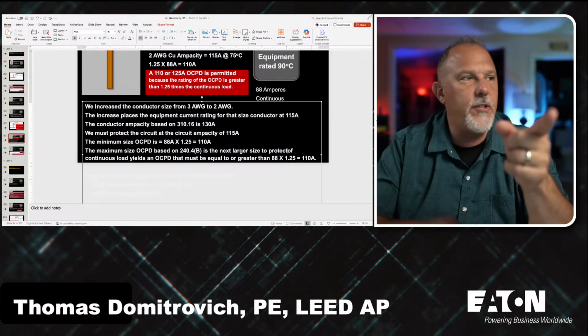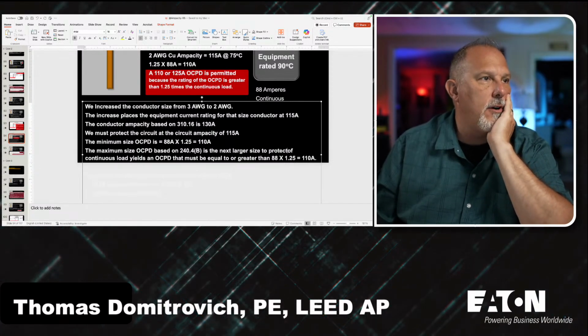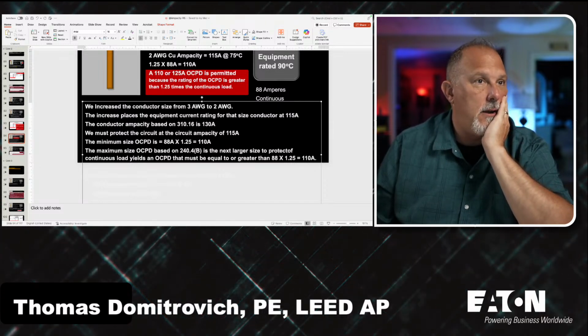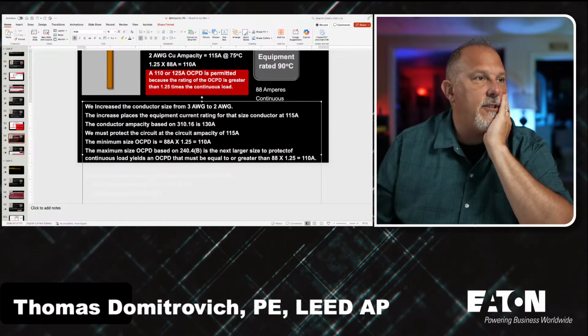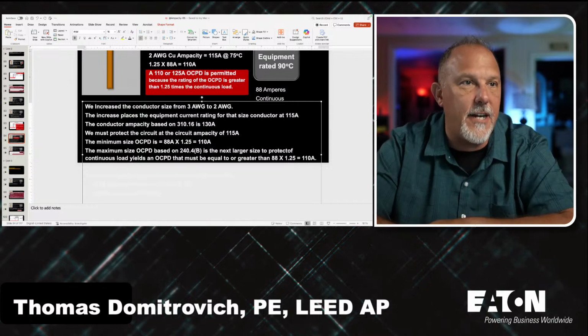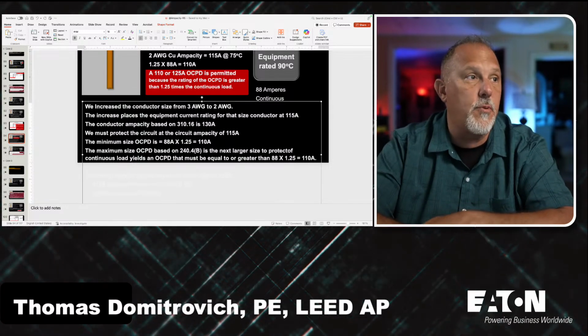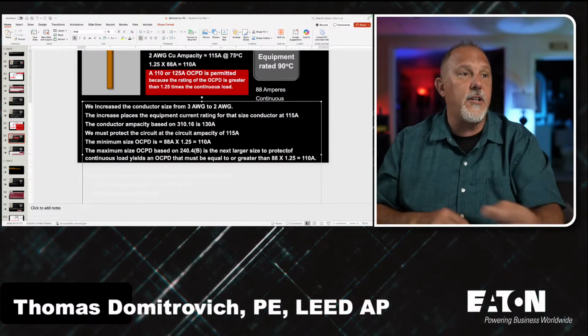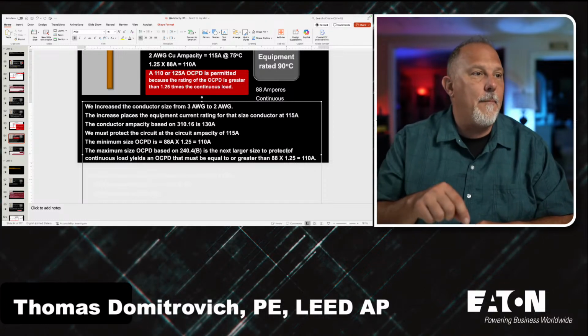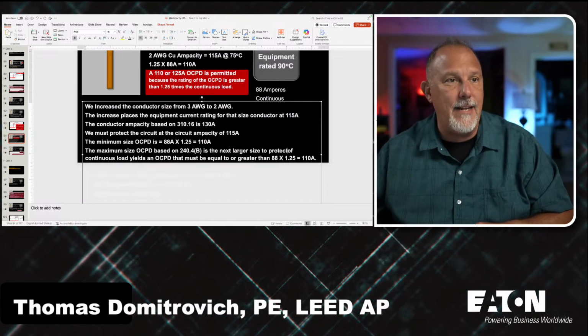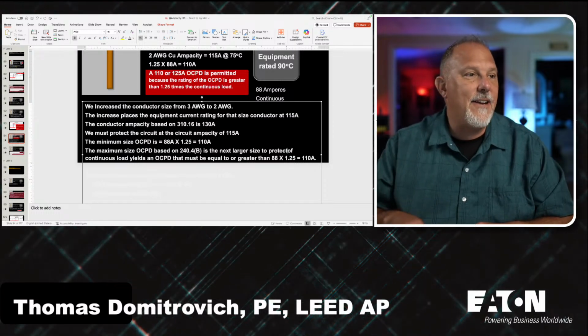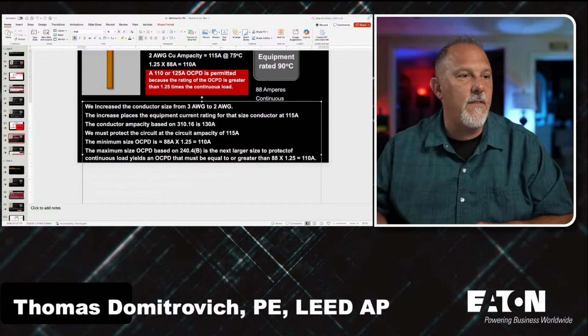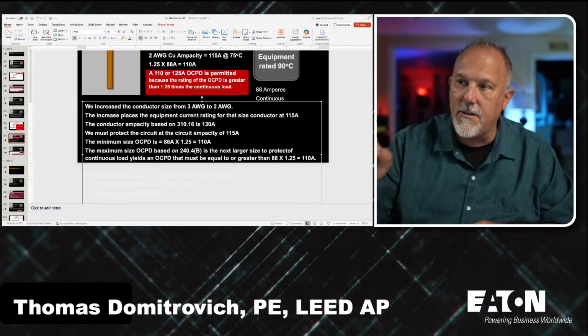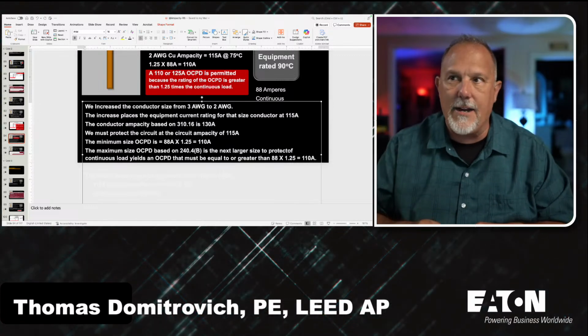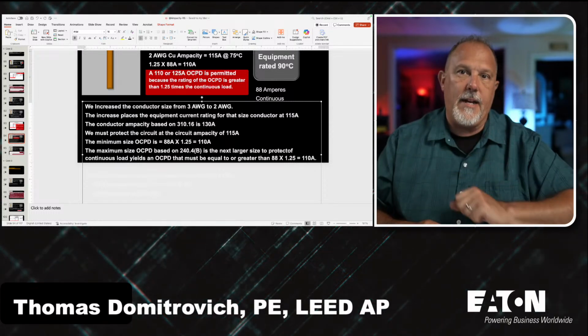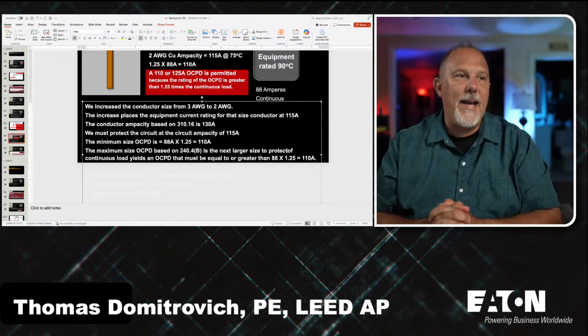Everything I've heard of with the 1.25, the 240.4 says conductors. The next higher standard overcurrent device above the ampacity of the conductor being protected shall be permitted to be used provided all the following conditions are met. The conductors being protected are not part of a branch circuit supplying more than one receptacle. The ampacity of the conductors does not correspond with a standard ampere rating. The next higher standard rating selected does not exceed 800 amps. If the overcurrent protective device is adjusted. So this is not a conductor value. I can't go to the next higher for the equipment rating. The ampacity of the conductor.